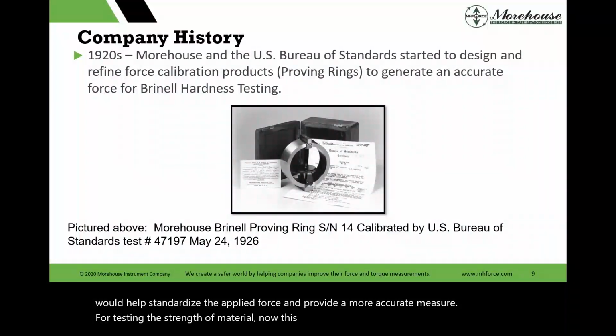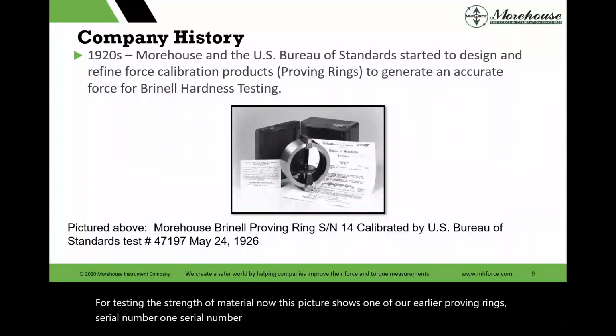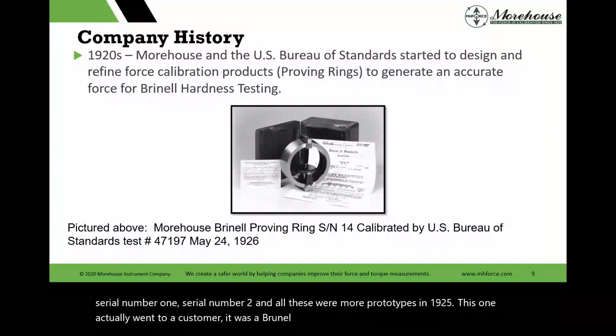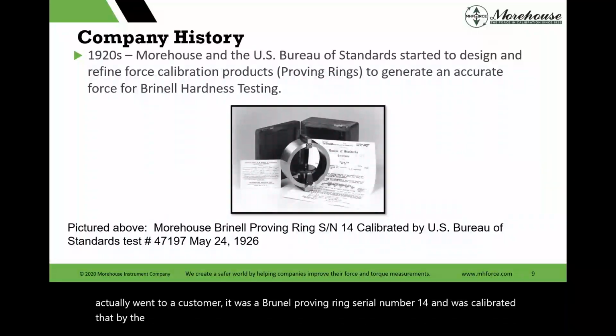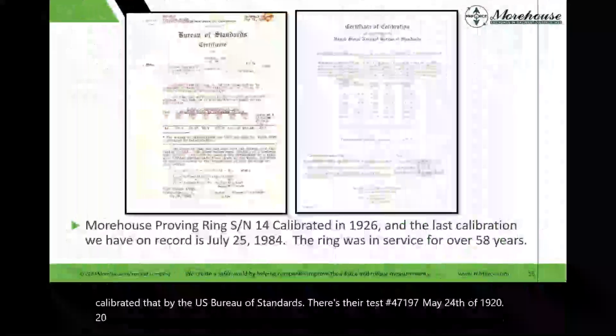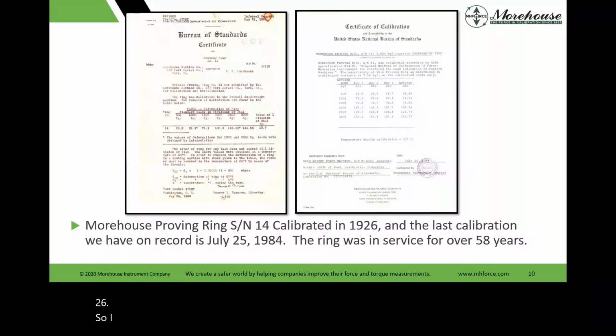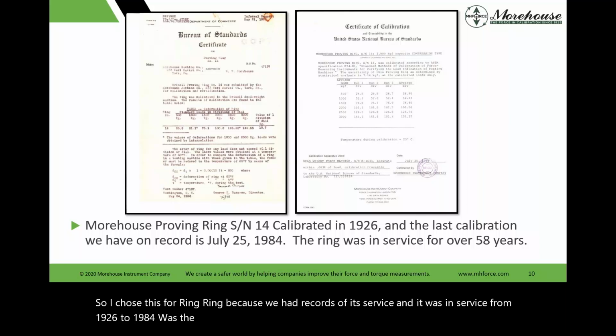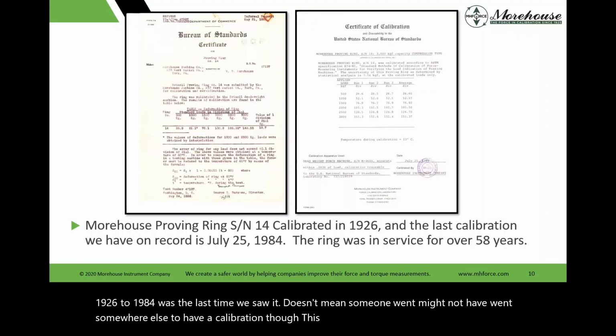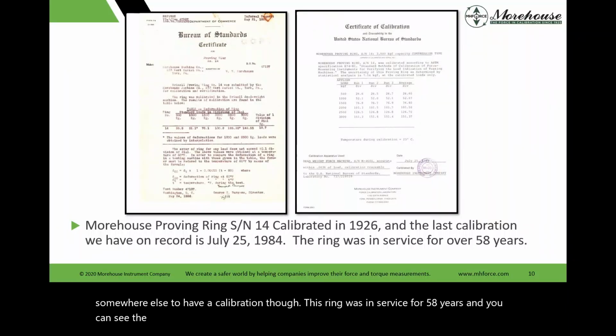Now, this picture shows one of our earlier proving rings. Serial number 1, serial number 2, and all these were more prototypes in 1925. This one actually went to a customer. It was a Brinell proving ring, serial number 14, and it was calibrated by the U.S. Bureau of Standards. There's their test number 47197, May 24th of 1926. I chose this proving ring because we had records of its service, and it was in service from 1926 to 1984, which was the last time we saw it. That doesn't mean someone might not have gone somewhere else to have a calibration, though this ring was in service for 58 years. You can see the certificate from 1926 to the certificate of 1984 there.